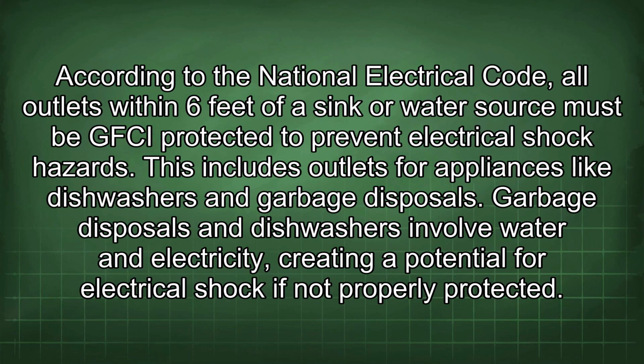According to the National Electrical Code, all outlets within 6 feet of a sink or water source must be GFCI protected to prevent electrical shock hazards. This includes outlets for appliances like dishwashers and garbage disposals. Garbage disposals and dishwashers involve water and electricity, creating a potential for electrical shock if not properly protected.